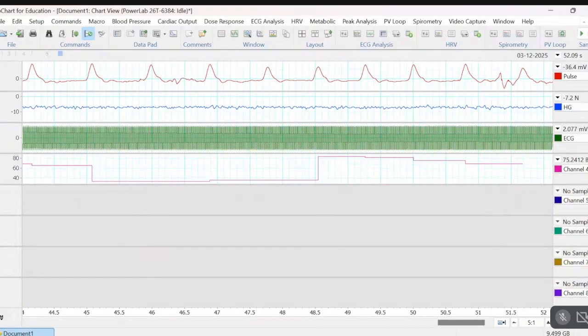Then I'll move to the next signal. I'll just stop. I'll remove the finger pulse. I'll show you one signal. I'll show you the hand grip. So I'll just go to the grip force. I'll do a zero. Certain sensors require a calibration. So I'll just put the grip force sensor that I showed you on a flat surface and do a zero.